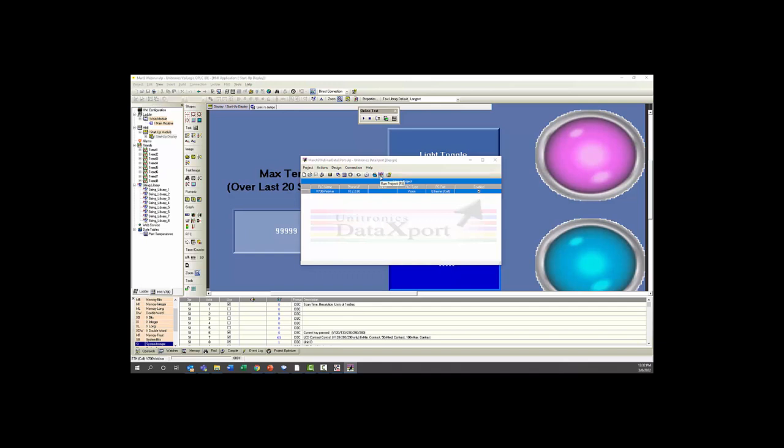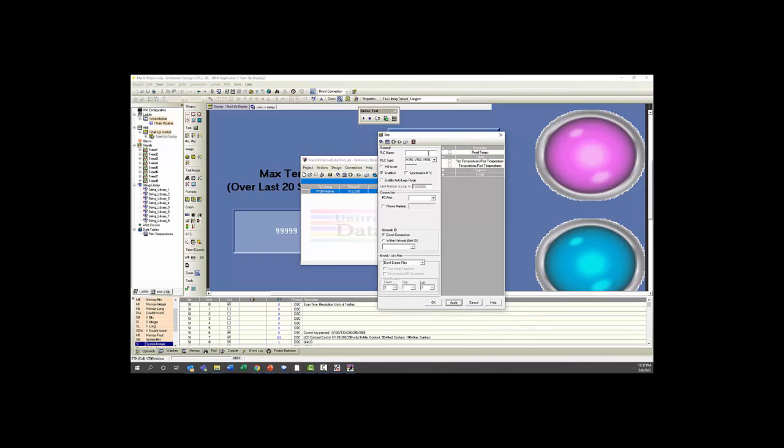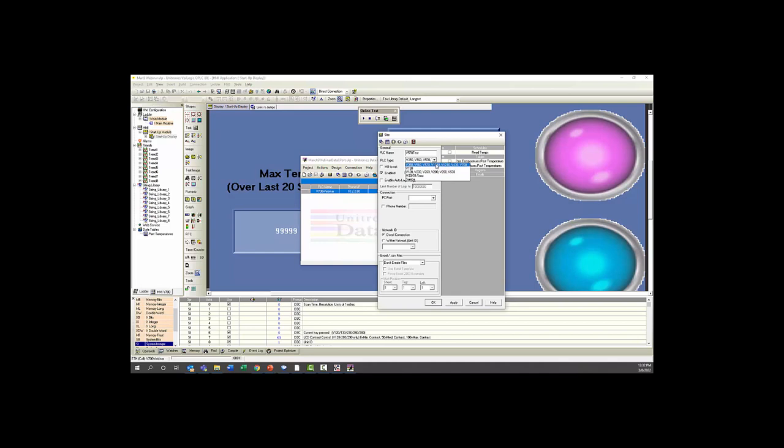To add a PLC, you would go to this icon here and select Add Site. This will bring up the following popup, where you would put in the PLC name. For this example, we're just going to call it V570 Test. You're going to make sure you have it selected from the appropriate series of controllers here. This is the Vision Enhanced Series. This is the Standard Vision Series, your M90 and Jazz, and your Samba Series controllers. By default, you can have it enabled. You can also choose to synchronize your real-time clock, and you can have it set a memory bit in the controller so that you know it has connected and pulled the data from it.